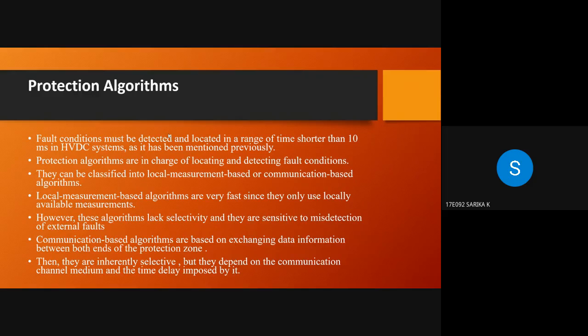First, local measurement based algorithms are very fast since they only use locally available measurements. However, these algorithms lack selectivity and they are sensitive to misdetection of external faults. Communication based algorithms are based on exchanging data information between both ends of the protection zone. Then they are inherently selective, but they depend on the communication channel medium and the time delay imposed by it.